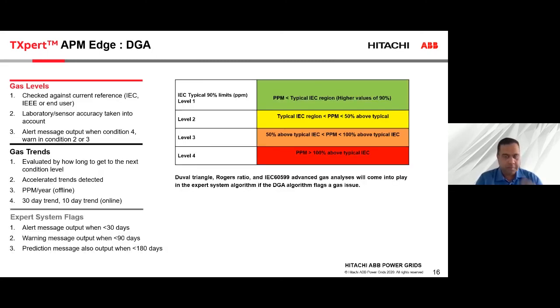So just to summarize, what we are doing now is checking the gas levels and the gas trends simultaneously. We check the gas levels against the IEC levels, IEEE, or even you can put in your own numbers. We also take into account the accuracy of either the sensor or the lab. And when we are breaching level 1, which is the typical IEC limit, if we see that the gases are rising at such a rate that they will reach condition 4, we will immediately alert the asset manager, and we will warn if the gas levels are in level 2 and level 3. And when we are doing simultaneous gas trend analysis, we evaluate how long it will take for the gases to jump from 1 to 2, 2 to 3, 3 to 4.